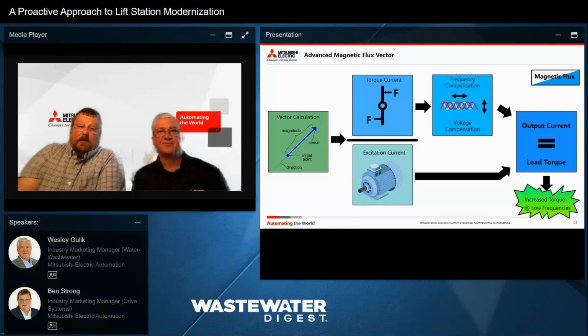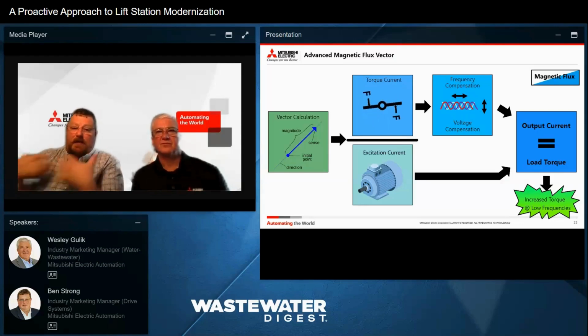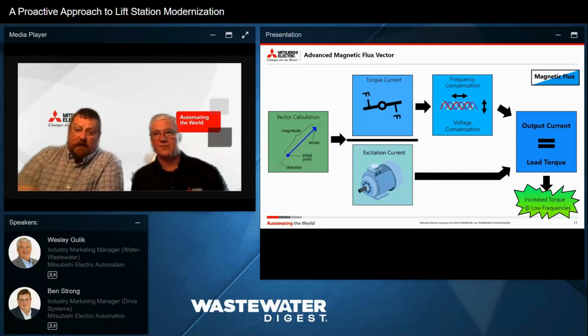If we switch it to a flux vector mode, we can do the calculation on current, and the drive will divide that current. This is the amount of current that's required to create torque, and this is the amount of current required to energize the motor so I have a magnetic field. Once I know that current, the drive can compensate the voltage and frequency so I get more control, increased torque at lower frequencies, and I'm going to use the energy I'm putting into the motor. I'm going to be more efficient.